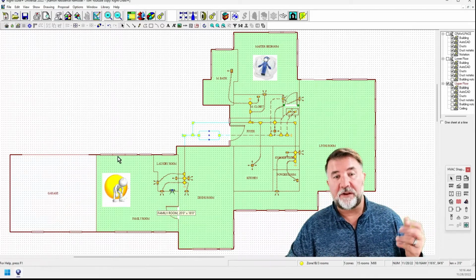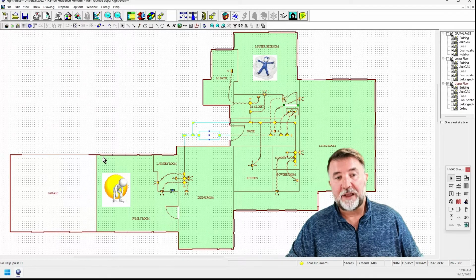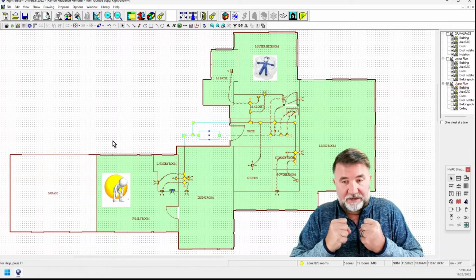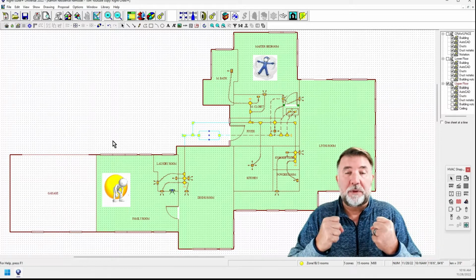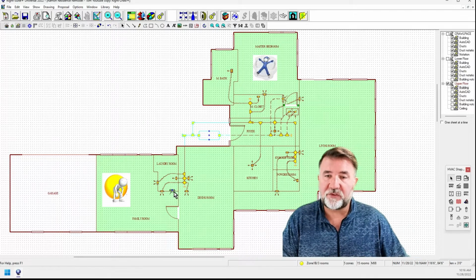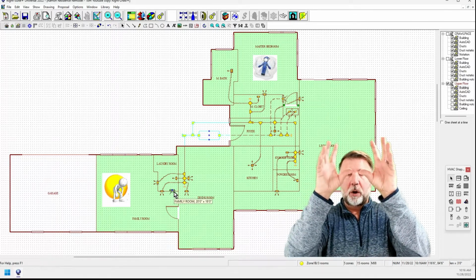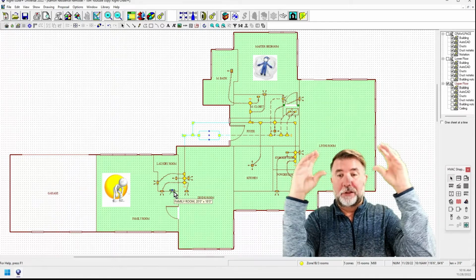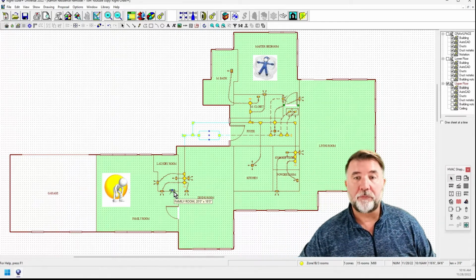Now, you always want to make sure your house in general is under slightly positive pressure. The benefit of that is to not allow air to be sucked in through cracks and crevices, because then that'll cause the heat and humidity issues even more. So you want a slight positive pressure. So this is called a transfer grill. It goes usually above the door, one on each side, and allows the air to transfer. Basically just an enlarged undercut.